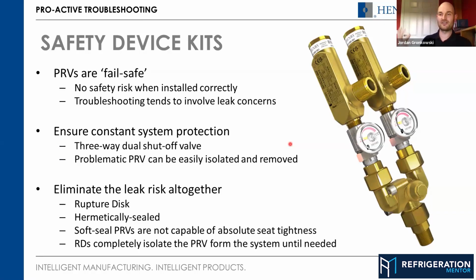Because again, that's affecting the back end of the valve, the spring especially, and especially on straight through valves where it goes in and fills up, and you can get corrosion on the spring, which will reduce the set pressure. So again, you don't want to have any restriction on top. I've seen some people leave caps on the top, plastic caps, thinking they'll blow off in the event of a discharge, which they may, but if they're tight, they may cause the valve to suddenly reseat again and jam. And you don't want to do that. So ideally, you'd have a little elbow or something on the top of the valve.